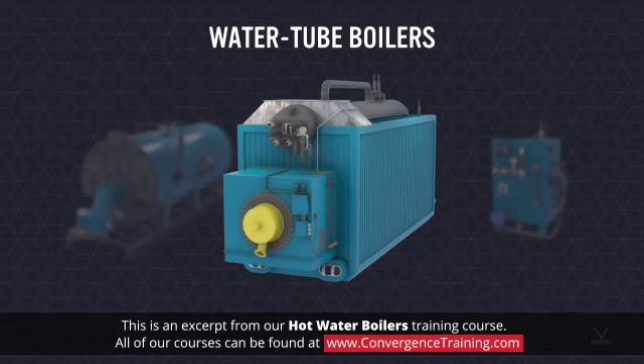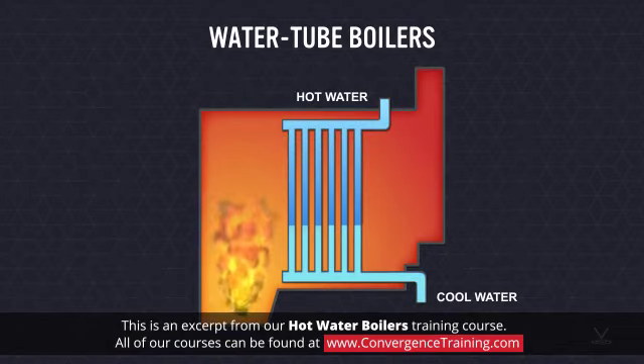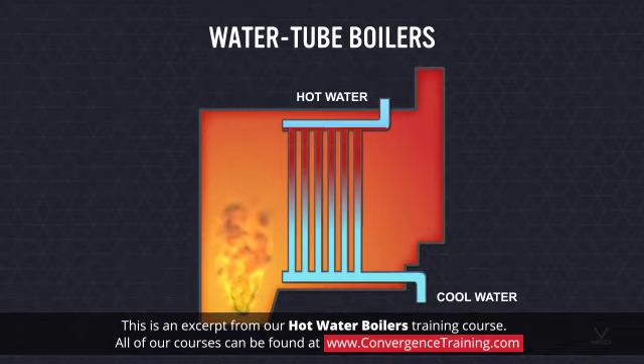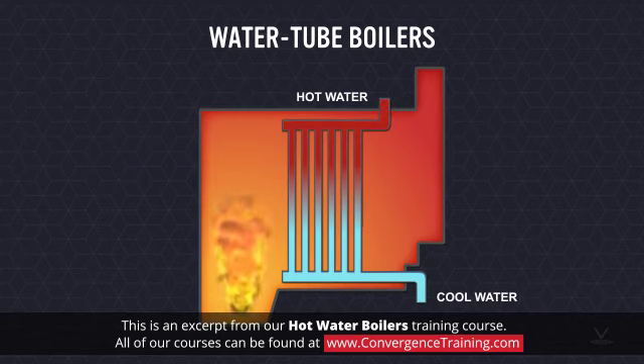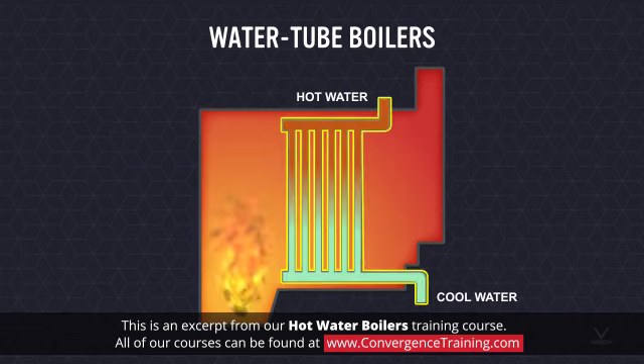In water tube hot water boilers, the water flows through a series of tubes that are surrounded by hot combustion gases. Heat still transfers from the hot gases through the tube walls to the water, but in the reverse direction.